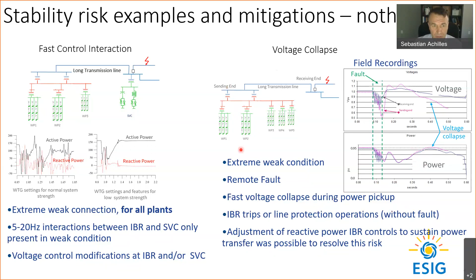This problem was resolved also by modifying the reactive power control in inverter-based resources to make sure there was enough reactive current in the system to sustain the power transfer when the power was increased. This plant has also been operating for many years stably. So these are two examples of the type of issues that you can see with weak grids.